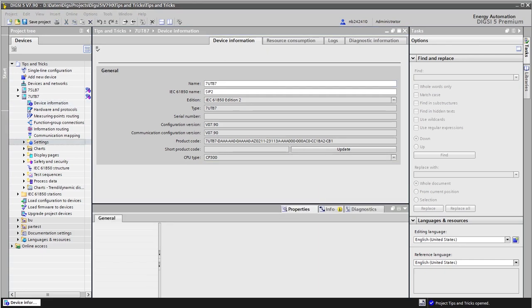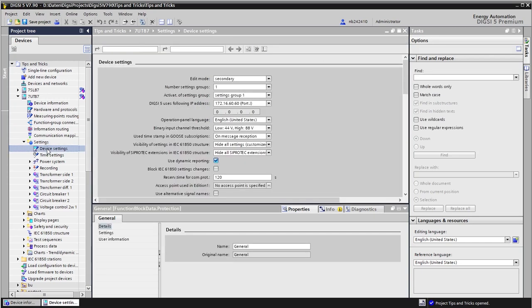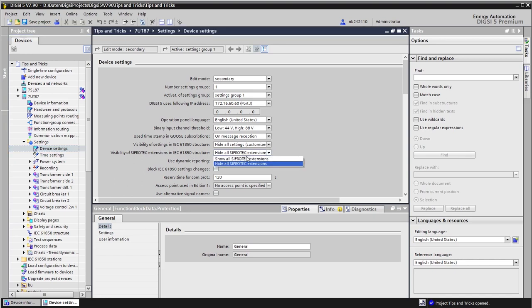Then let's go to the device settings, the general settings here. Here we need to show all Siprotec extensions because some of them are required for the parallel voltage regulation. It is this setting here and we have absolutely to set it to show all Siprotec extensions.